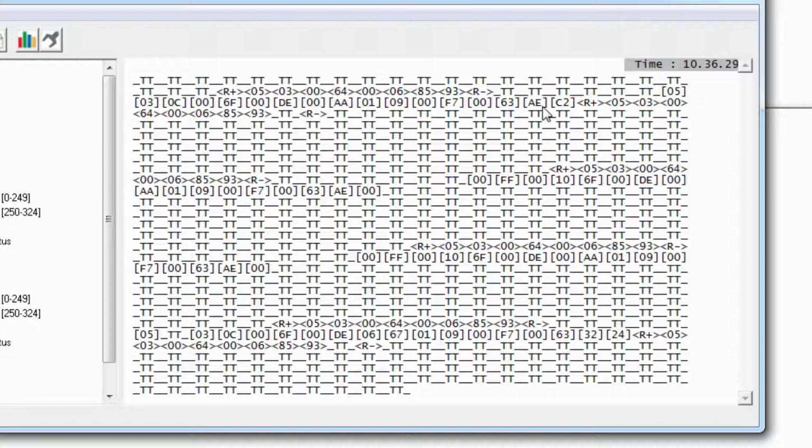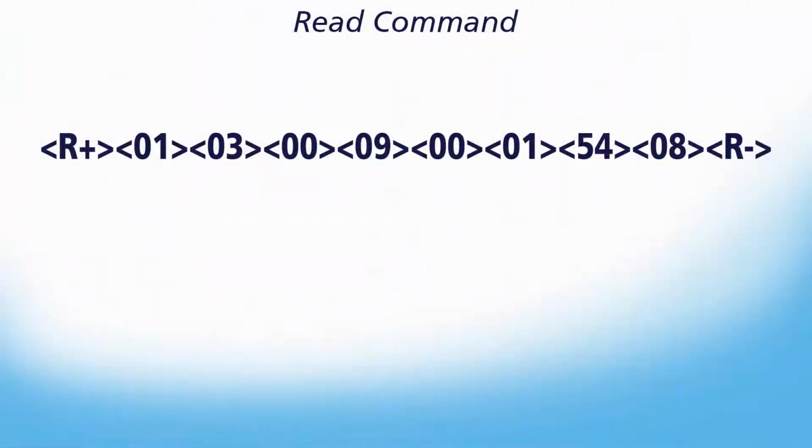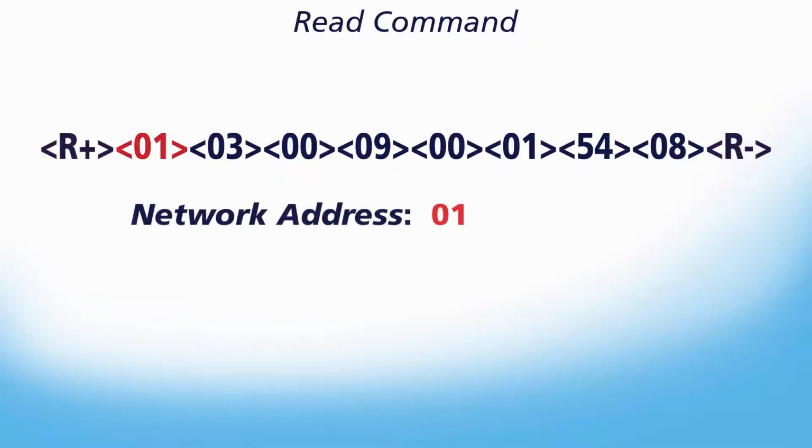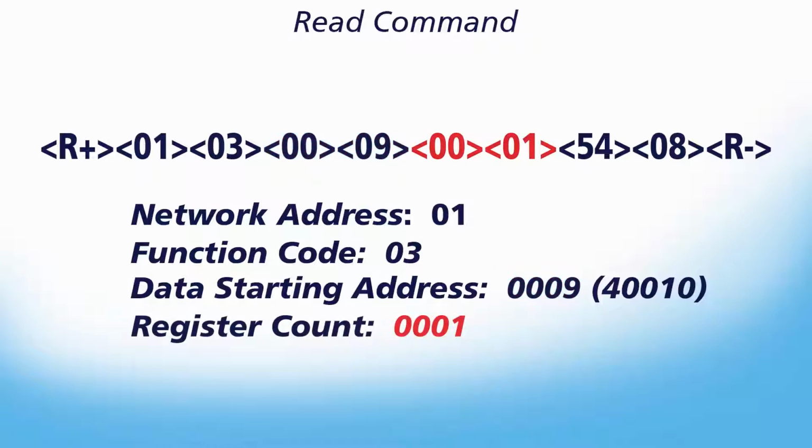So now we'll do a quick overview of the message composition. In the case of a master sending a command out, in between the R plus and R minus, we have a series of characters in arrow brackets. This message represents what a typical read command would look like. The first part is the node address on the network, which is 1, then the function code of 3, and the next several characters refer to the data requested or being sent.